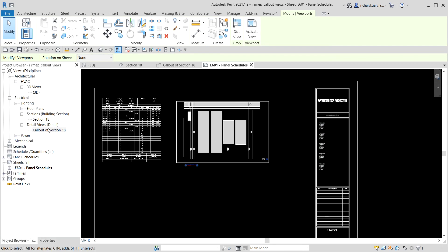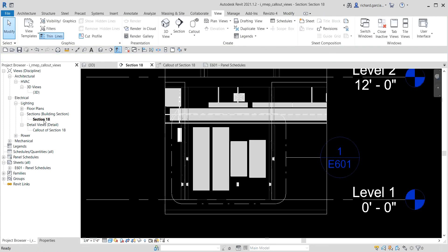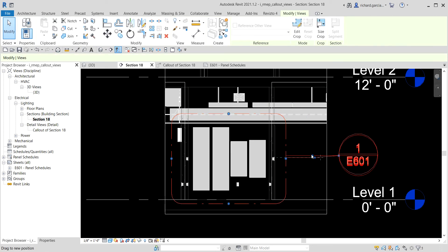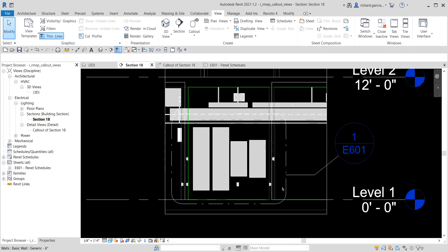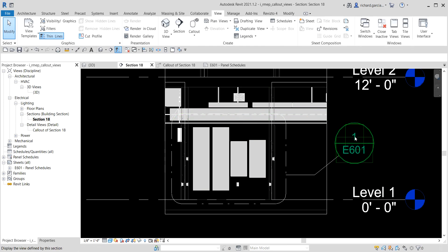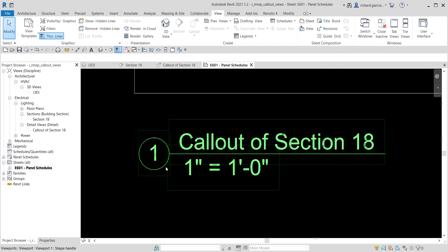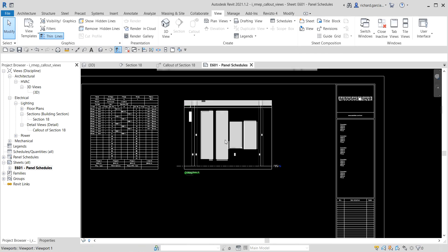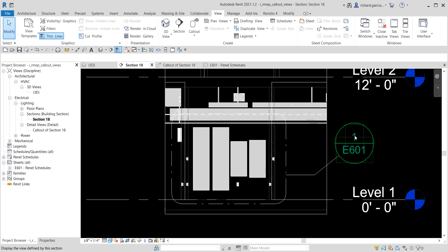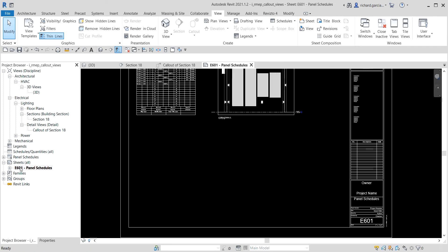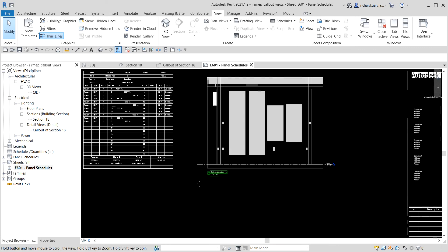Now if I go back to Section 18, you'll notice the callout bubble now has a detail reference — it says E601, detail number 1. That means the callout can be found on sheet E601, detail number 1. You can double-click sheet E601 from the project browser and look for detail number 1, which is this callout. This is how you identify which callout corresponds to which sheet and detail number.